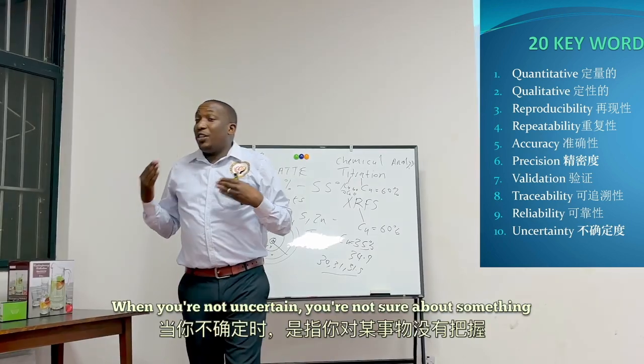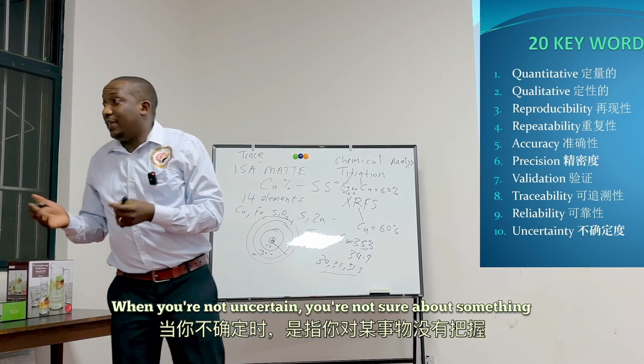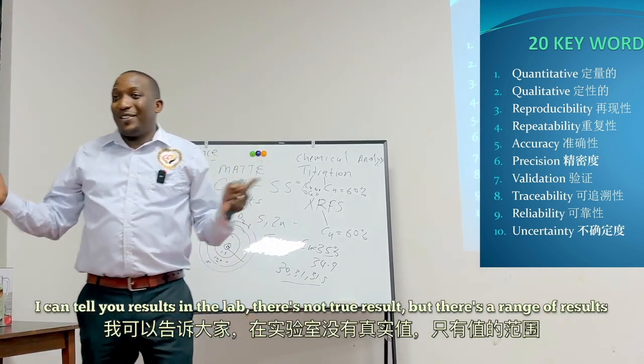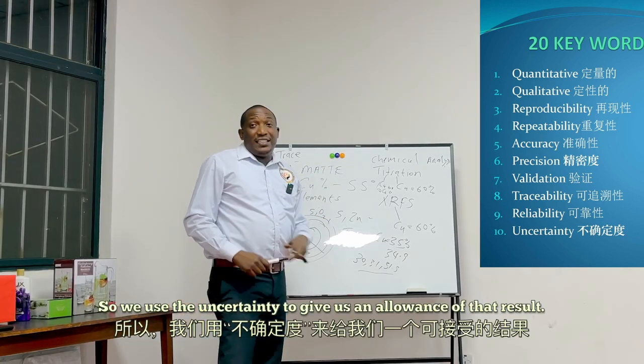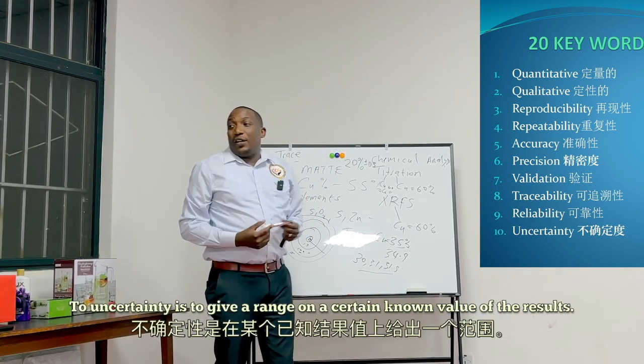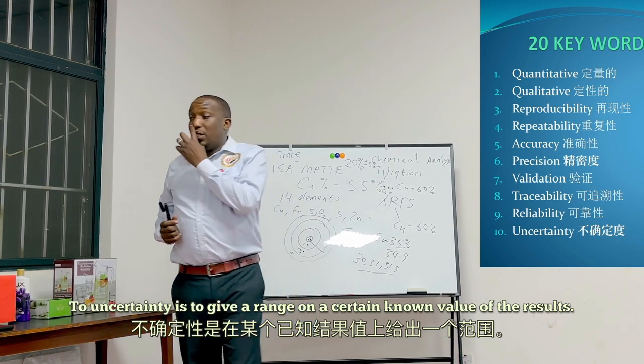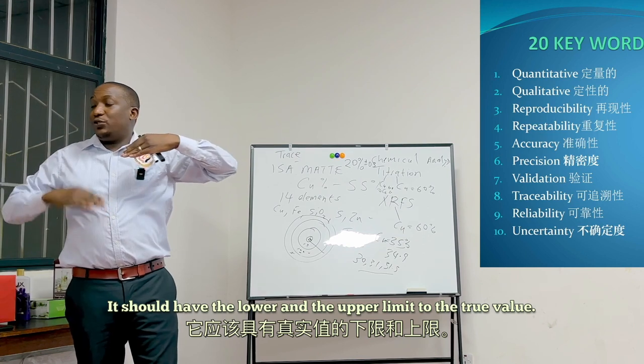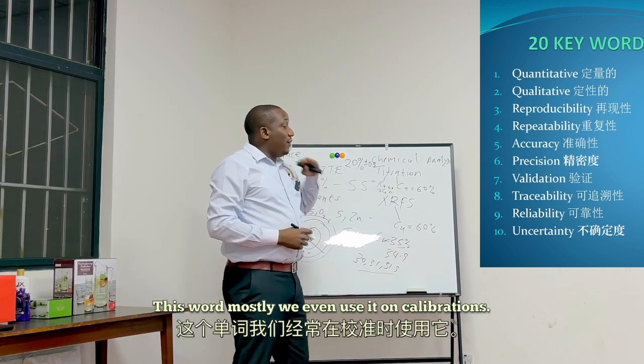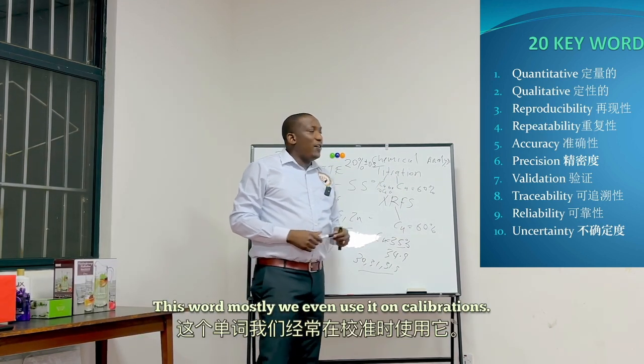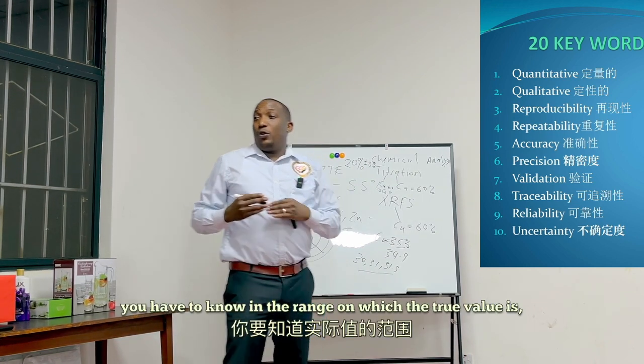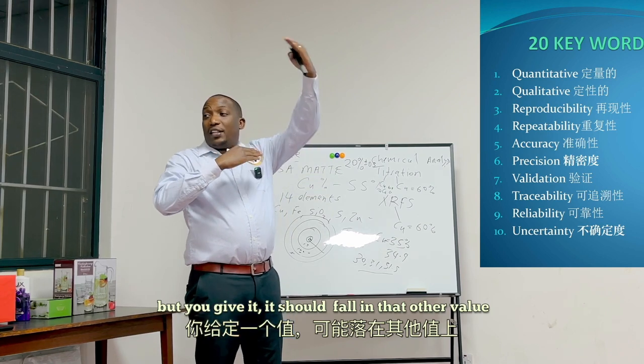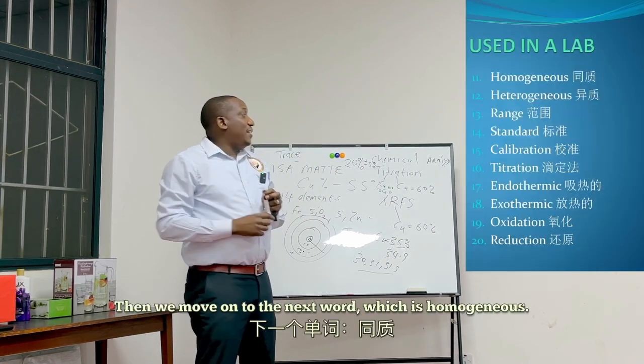The tenth word is uncertainty. When you're uncertain it means you're not sure about something. In the lab there's no single true result — there's a range of results. We use uncertainty to give an allowance on that result. Uncertainty gives a range on a certain known value; results should have a lower and upper limit relative to the true value. We mostly use it in calibrations — when calibrating an instrument, you have to know the range in which the true value should fall, plus or minus from the true value.